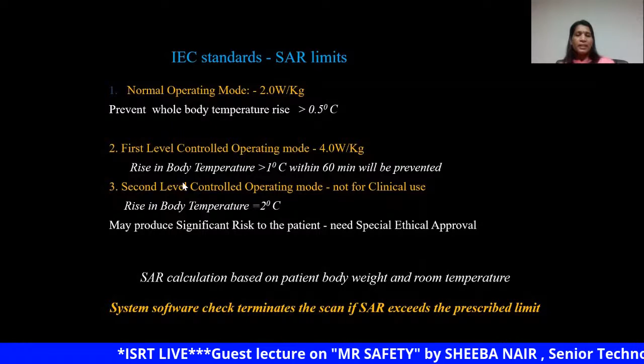But in certain pulse sequences, we have to enter the first level mode. Especially the steady state sequences will work in the first level mode. In such a condition, the total energy deposition is permitted up to 4 watt per kg, and the system will terminate the examination when the body temperature increases above 1 degree centigrade. The second level mode is not for clinical use. It is for research purposes, and in this mode the body temperature can rise 2 degrees from its initial temperature.